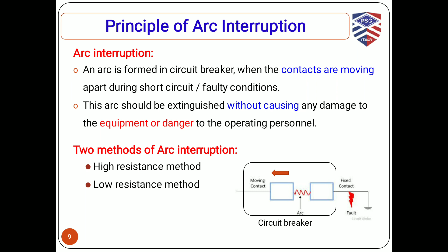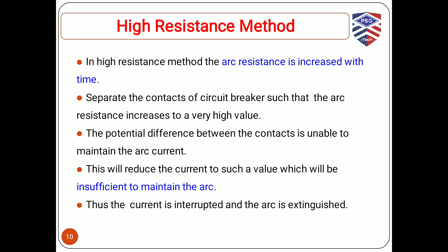First is the high resistance method. By increasing the arc resistance, we try to interrupt the arc. When we separate the circuit breaker contacts, the arc resistance increases to a high value. So the potential difference between the contacts is unable to maintain the arc current. When we increase the resistance, the potential across the contacts would be insufficient to form an arc, so the voltage gets reduced. This will reduce the current also because of the high resistance, so the current would be insufficient to maintain the arc. The arc would not be maintained, which means the arc can be easily interrupted.